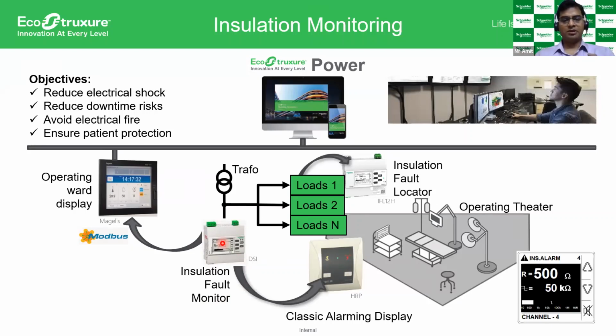Because Mr. Biju has also highlighted that 30 milliampere is dangerous for a normal human being, but for a patient, even 5 milliampere is very dangerous. It's a dangerous situation. So at that time the insulation monitoring device will give an alert notification that socket number 2 is faulty, so don't use it. At the same time it will show your socket number as well as the fault level in kilo ohms, and reduce electrical shock, downtime, everything.